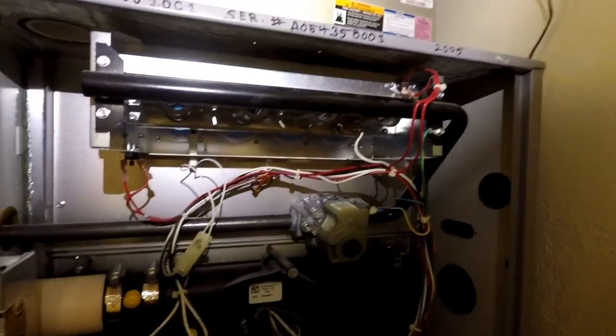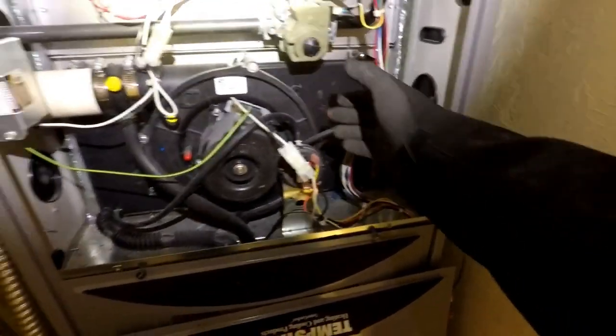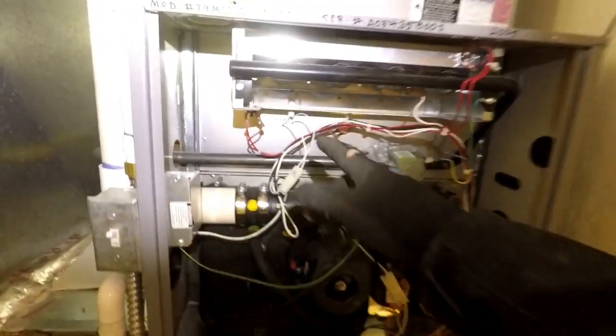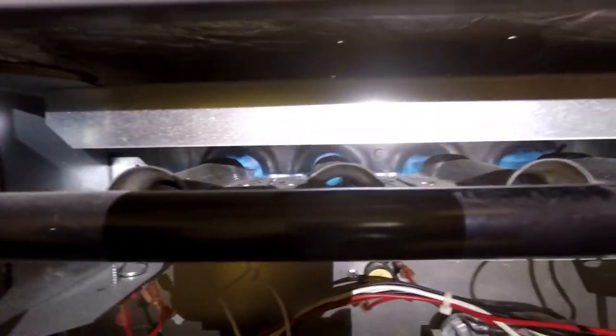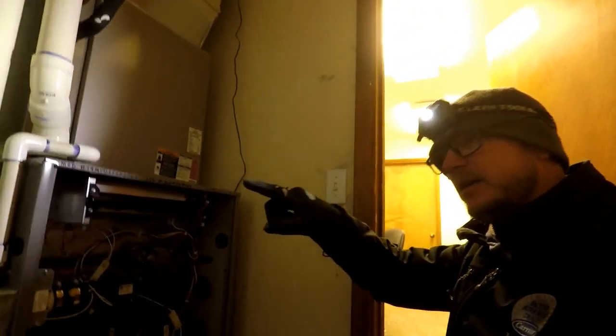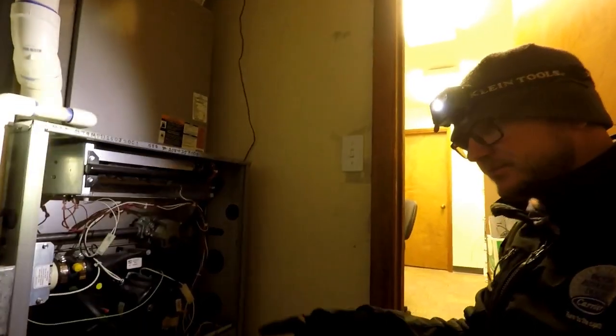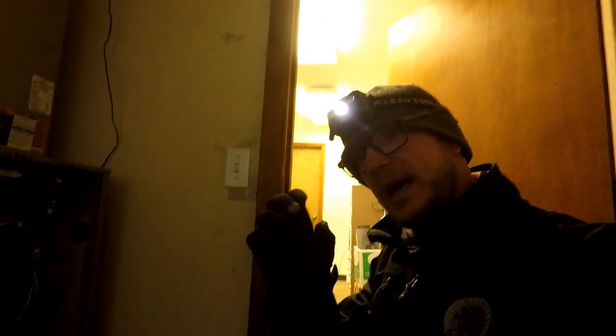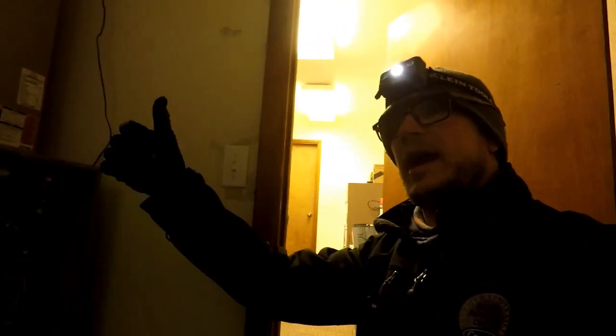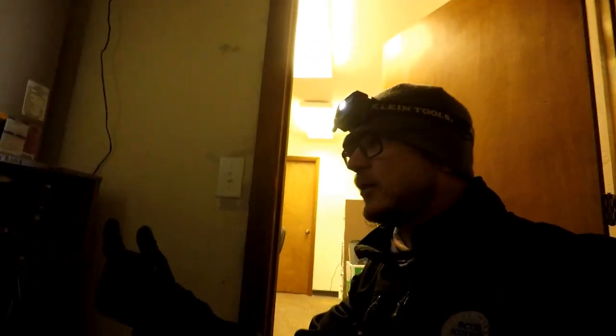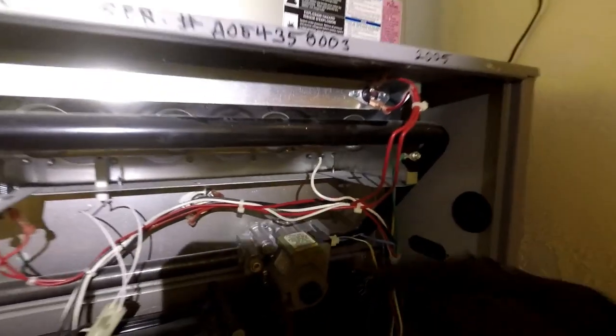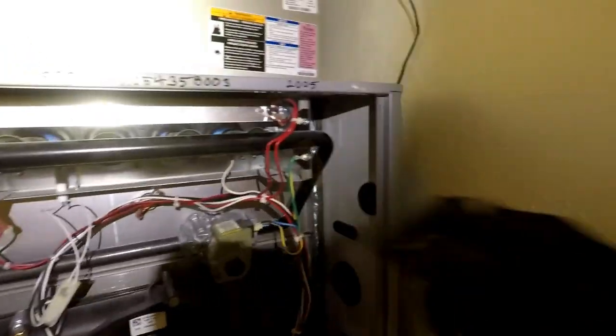Another thing that could cause it to roll out is above this heat exchanger, because this is called your secondary heat exchanger behind that box. The primary heat exchanger, if you look at those holes, you see a bunch of round holes, and those just have tubes inside of them that go serpentine back and forth. And if one of those gets a crack in it, and that crack starts to expand and open up as the blower is blowing air up through there, if it pushes air inside that crack, that also could push that flame back, right? It puts air inside that pipe and pushes that flame back into here.